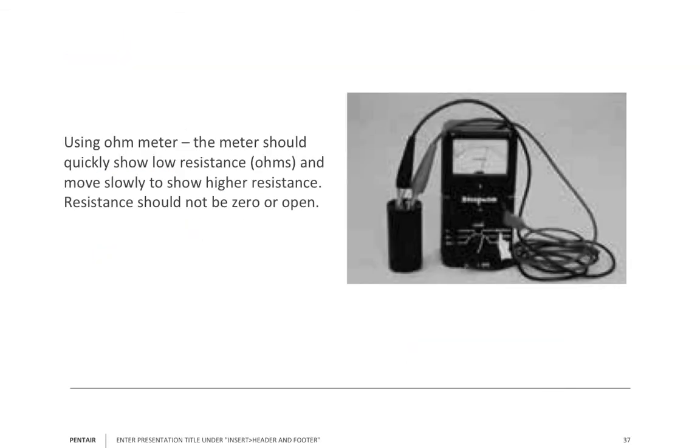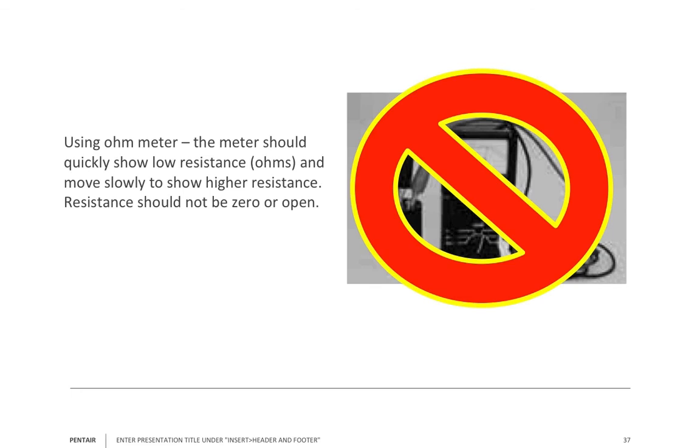This test, like I said, the old Simpson, only tells you that it's seen the voltage and the capacitor is trying to store it. Nowhere can I find out what my microfarads are. So this test, I'm not a big fan of it.